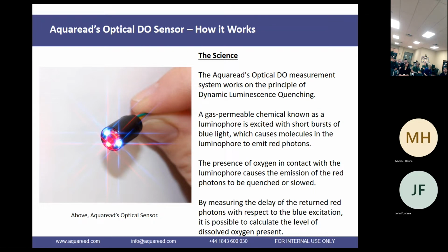The calibration of the sensor is done in one of three ways. You can do a 100% saturated oxygen calibration: you put the sleeve on, moisten a towel, and place it over the sensor. That gives you 100%. We do a zero oxygen solution, which is the zero value, or you can calibrate it using gas. Some customers use gas because it's very quick. The calibration process will extract oxygen from the DO cap, or it will oxygenate the sample. So the calibration is basically giving a zero value and a 100% value to calibrate against, and that's the range.